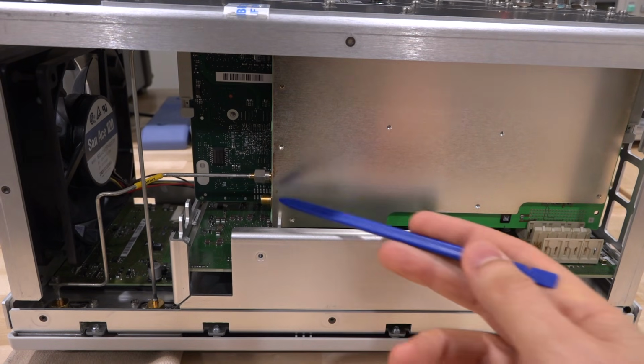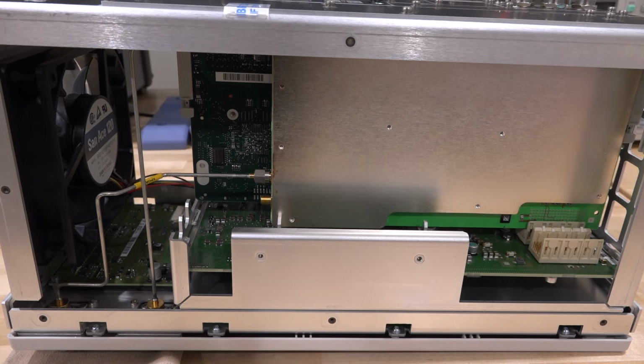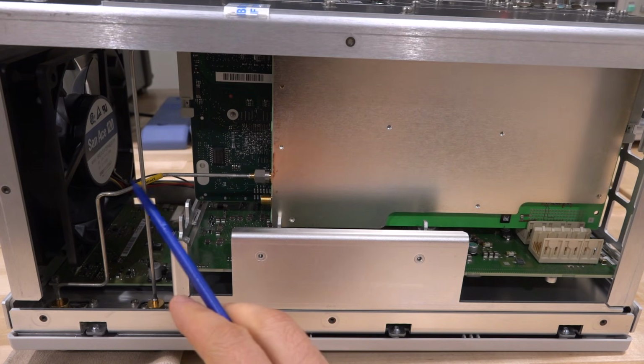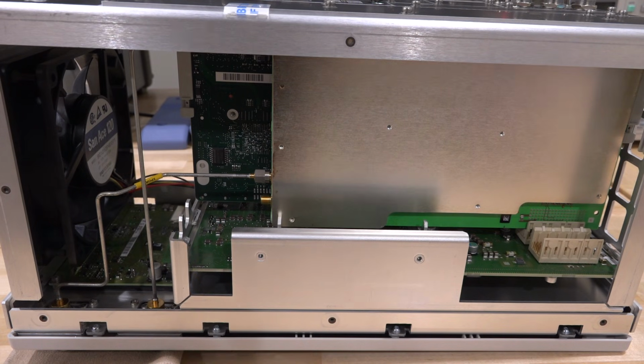I'm not sure, and this could be some kind of an LO signal that goes between the two, or maybe an IF signal. So having said that, you can see that these two coax cables cross each other on a 90-degree angle, most likely on purpose to reduce EM coupling to each other, because the magnetic fields will be perpendicular. So this is needed perhaps for a dynamic range that this instrument needs to have.